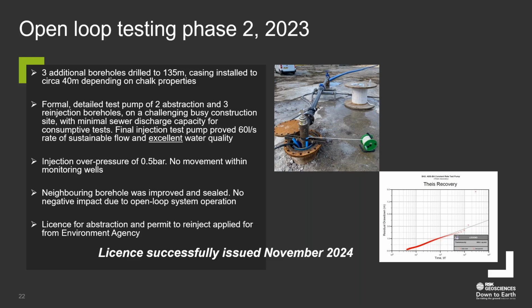But water quality is a very, very important aspect of any open loop system. If you have high iron or manganese or one or two other minerals within the water, it can cause problems. That wasn't present here. So during the test, we were pumping at 60 litres a second, re-injecting all of that back to the 3 injection boreholes with a bit of overpressure of about half a bar. No movement of the groundwater was detected within the 2 monitoring wells, so that groundwater level is all completely contained beneath the clay layer. There was no bad impact on the neighbouring borehole.